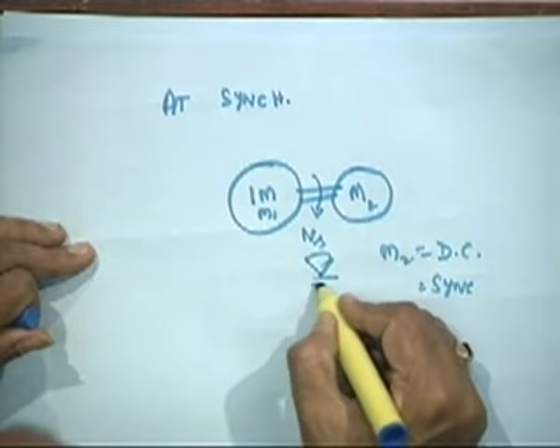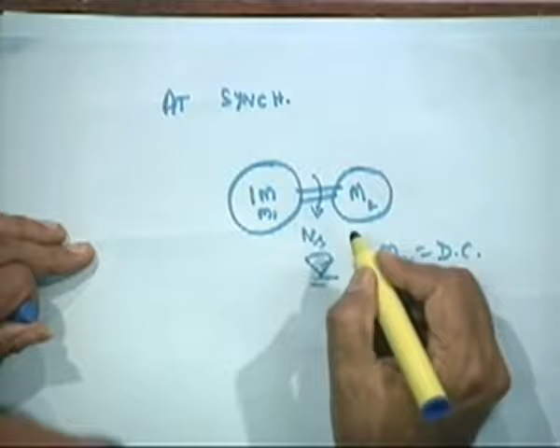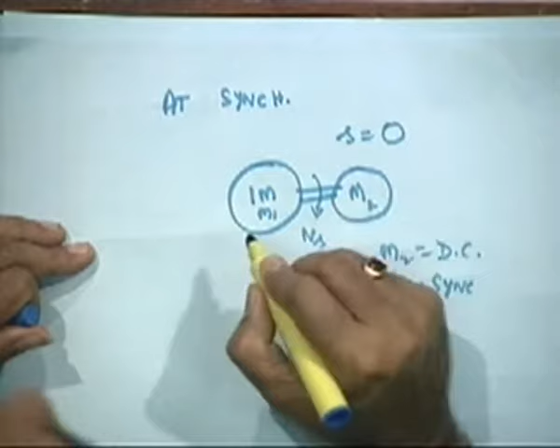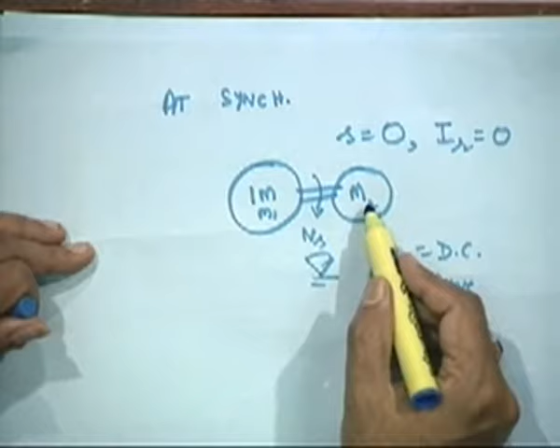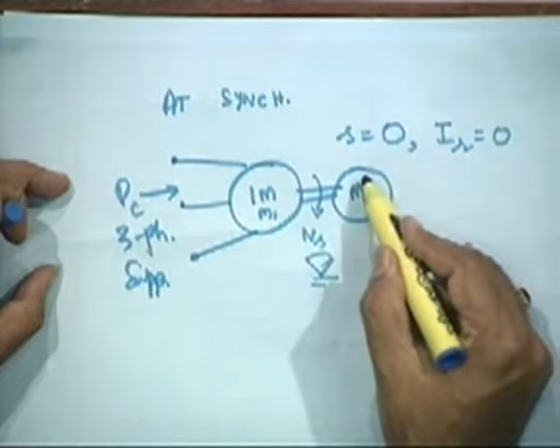That means normally you use a stroboscope or something so that you ensure it appears exactly stationary against the strobe. So when N equals NS, that means slip is definitely equal to 0. Therefore, when slip is 0, rotor current is 0. That means the friction windage is now supplied by the drive motor, right? And only this machine will give you the core loss PC, which is corrected. That means it is run by the 3-phase supply. It will be the induction motor, and the DC motor if you are using one. So this will give you the friction windage loss.